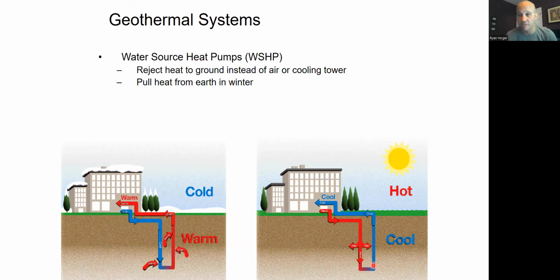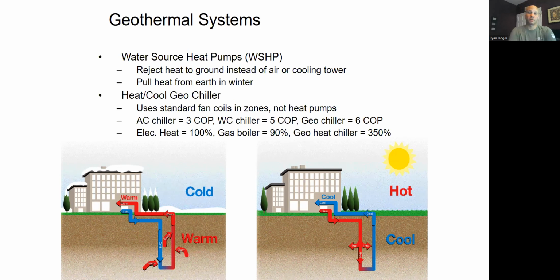And maybe the cooling tower doesn't have to run in June, but maybe it does have to run in September, right? So the same idea that I have with these water source heat pump jobs being coupled to geothermal loops, I could also do that with a chiller. So instead of having water source heat pumps in all the individual tenant areas, I could have fan coils and air handlers in the tenant areas like a normal building would have. And then in the penthouse, or in this case, probably more likely in the basement, I would have my geothermal chillers. And those chillers would be sending water to the ground, condenser water in the summertime.